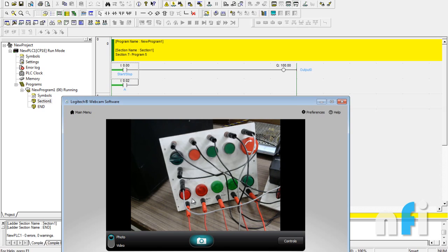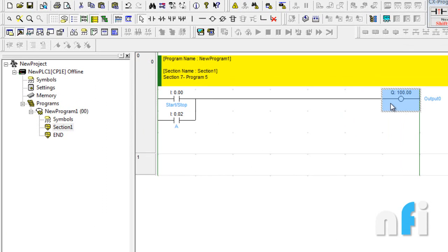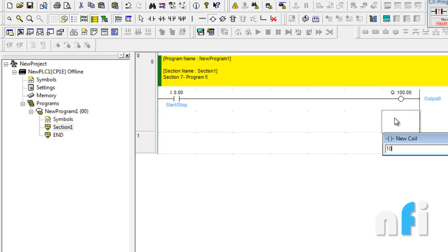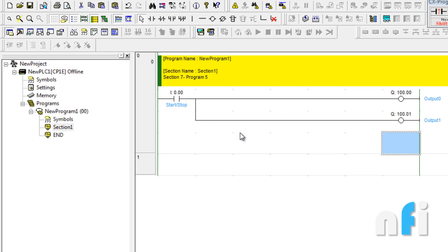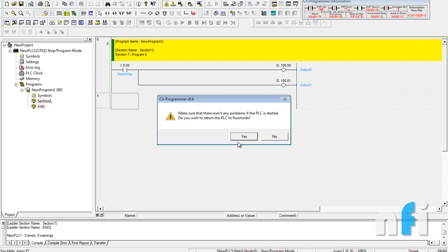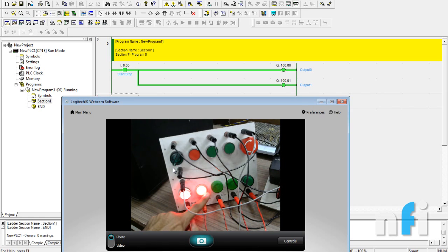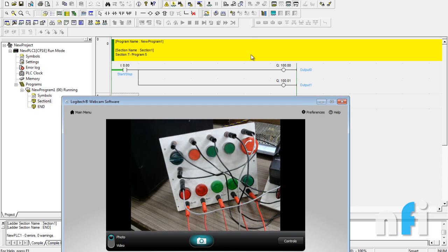Here we are using indicators, but you can also use a relay to turn on a motor, alarm, or solenoid. Now exercise four: design a parallel output circuit such that when input 0.0 is on, outputs 100.0 and 100.1 should both be on. Delete the previous rung. Now add a coil in parallel — write the address, press Enter, and it is automatically connected in parallel. Transfer to PLC with Ctrl+T. Now if I turn on this input, two outputs are on. You can add a third output in parallel as well.